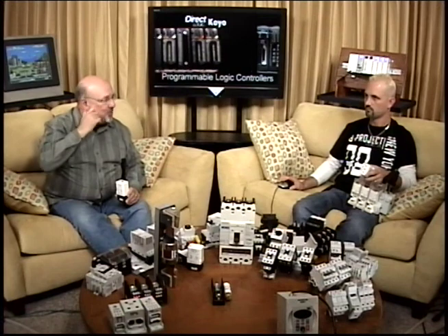We also have one of the ProSense relays that'll do alternating for pumps, like a duplex pump circuit. And then especially in pumping applications, you're going to have seals, and there's a leak detector. We sell a relay that'll monitor the leak detector and shut the pump down if you detect a leak in the gasket or material or whatever. And then our next slide. Had to put a wiring diagram in here. He loves his wiring diagrams. We're showing the phase monitoring relay, how it would wire up to the power going to the motor and everything.